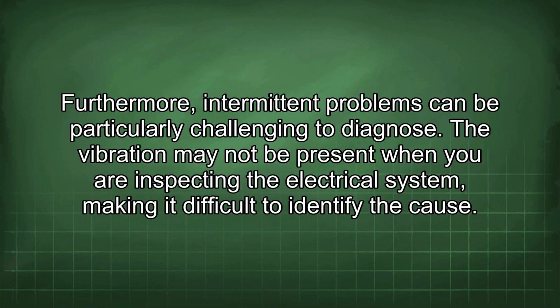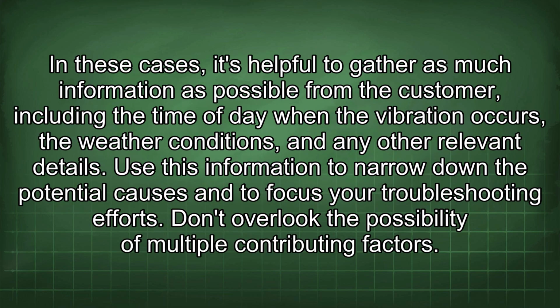Furthermore, intermittent problems can be particularly challenging to diagnose. The vibration may not be present when you are inspecting the electrical system, making it difficult to identify the cause. In these cases, it's helpful to gather as much information as possible from the customer, including the time of day when the vibration occurs, the weather conditions, and any other relevant details. Use this information to narrow down the potential causes and to focus your troubleshooting efforts.